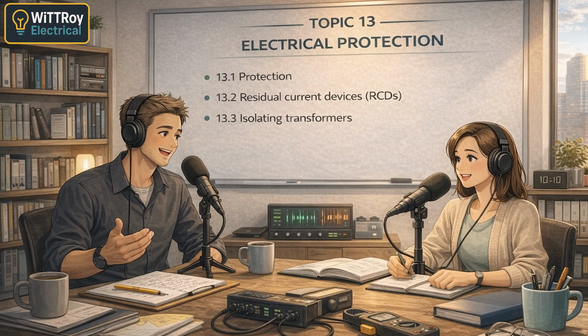That's common. Let's clear it up. Overload protection is the more sensitive type. Meaning it trips earlier. Exactly. Overload protection operates within 4 hours at 1.5 times the design current. 4 hours sounds long. It does, but remember, this is for overload conditions, not short circuits. Oh, okay. Overload protection limits long-term heating.